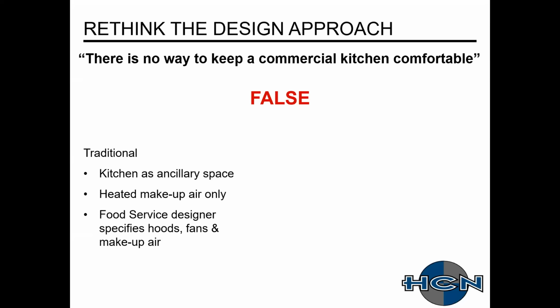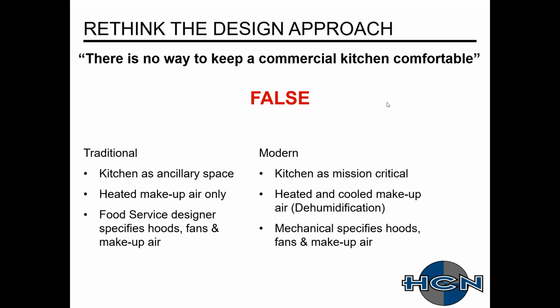So like I said, your traditional design, it's an ancillary space. You're typically just doing a heated makeup air. And then in some places, they're actually allowing untempered makeup air. And then, like I said, usually it's a food service designer, a consultant, someone on that side that deals with the equipment layout, who is specifying the hoods, and now they're starting to specify fans and makeup air. Whereas hopefully I can help you guys make this more mission critical.